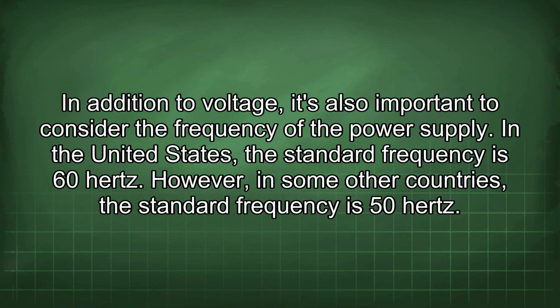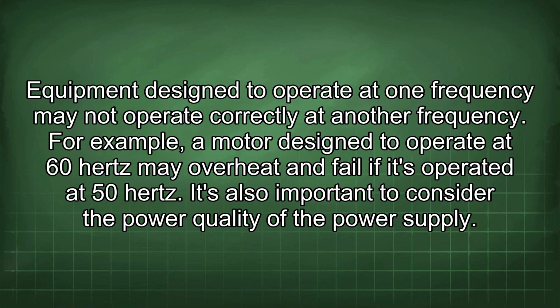In addition to voltage, it's also important to consider the frequency of the power supply. In the United States, the standard frequency is 60 Hz. However, in some other countries, the standard frequency is 50 Hz. Equipment designed to operate at one frequency may not operate correctly at another frequency. For example, a motor designed to operate at 60 Hz may overheat and fail if it's operated at 50 Hz.